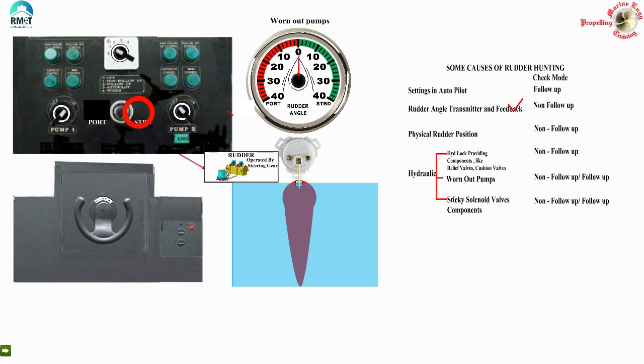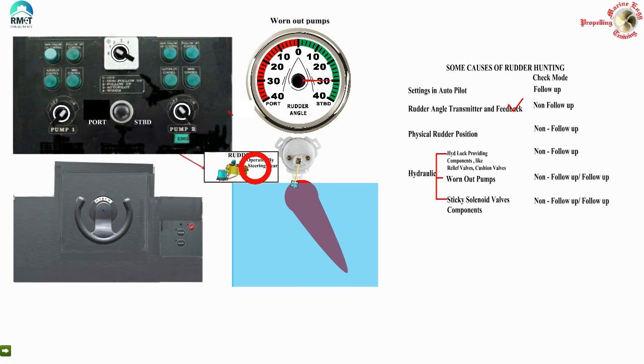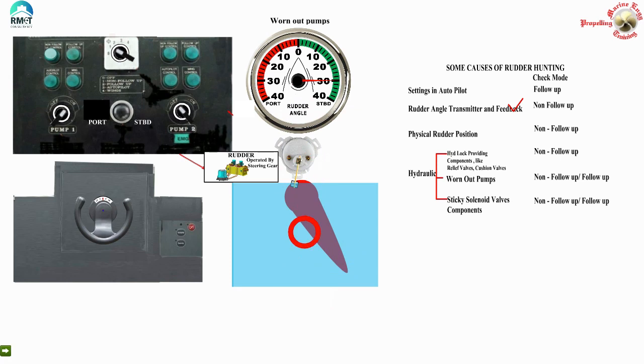Take the rudder to hard starboard using non-follow-up and measure the time from midship to hard starboard - or you can do it from hard starboard to hard port. Compare this reading with SOLAS required timing. In this case, if the expected time is 14 seconds but it took 20 seconds, obviously the problem is the worn-out pump.